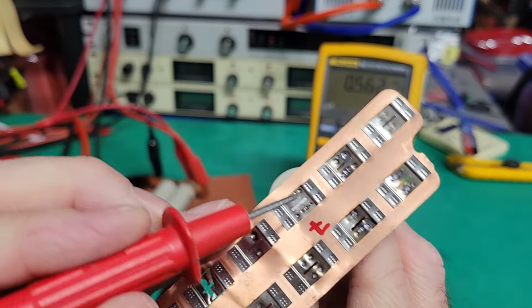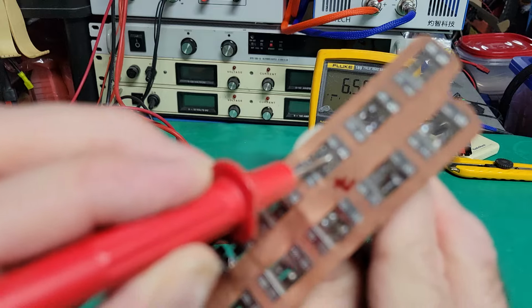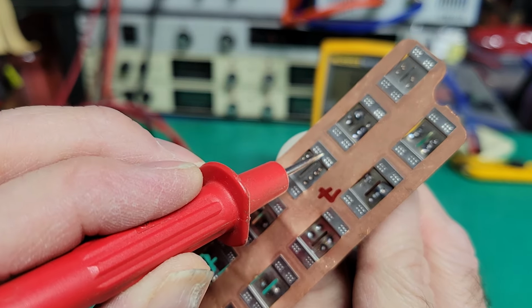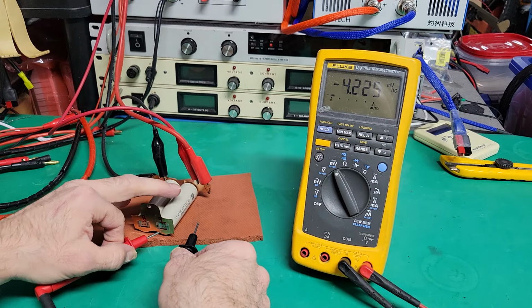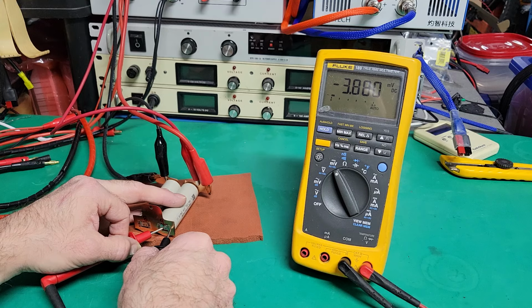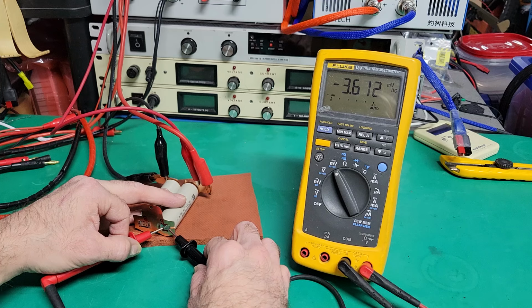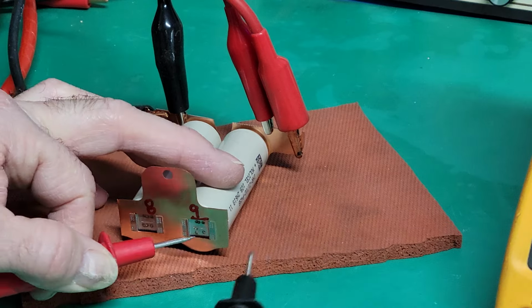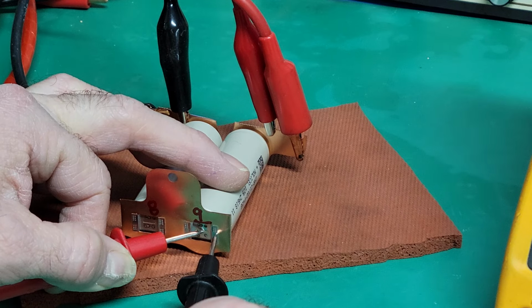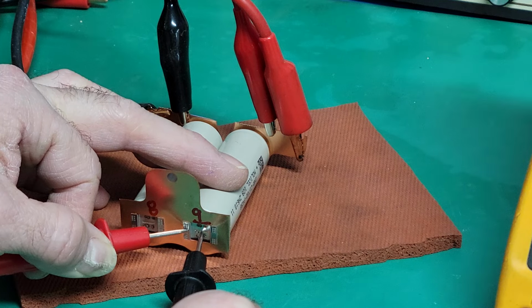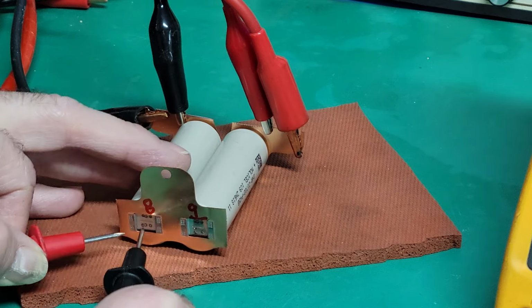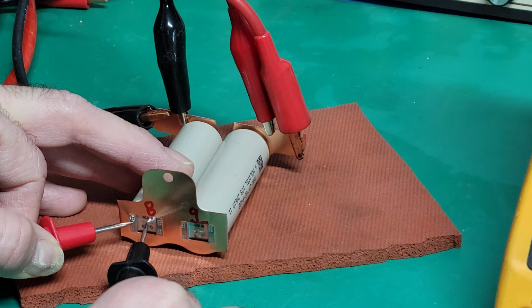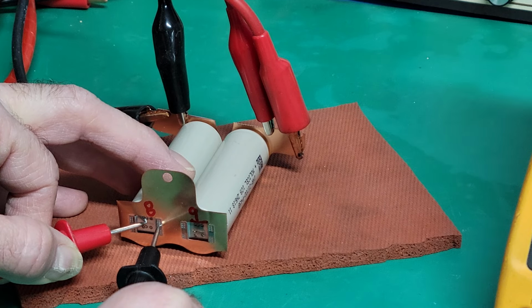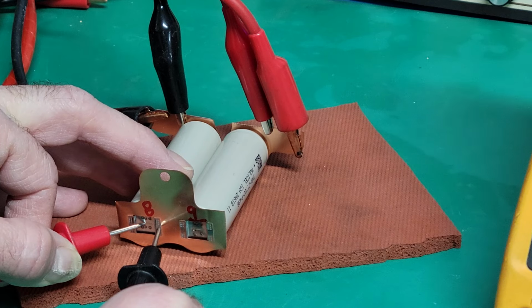So this is 3.8 millivolt between this area and this part here. So I will check compared to the copper next to it. It's about the same as when I measure directly on the copper. I'll try to zoom in a little bit. All right, so measuring from the middle to the side here, 3.7 millivolt, and for the next one, it's about 3.7 millivolt too. And the second weld here, 2.9 and 3. So we can average to about 3.2 millivolt at 10 amp, which means 0.32 milliohm resistance.